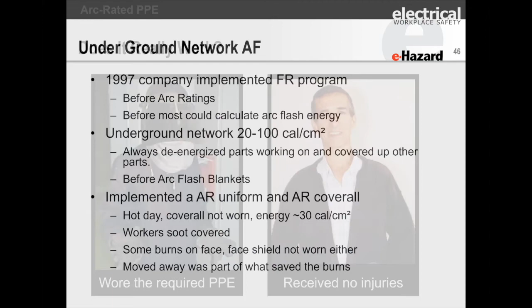Arc blast blankets are now becoming more used. They have failure points and details that can protect. In this case, we used this blanket, and after the test, the one on the right had no blanket intact, while the other one, the blanket was intact, and there was a big difference in body burn. If you can cover up the arc flash hazard of energized parts that can't be de-energized while working in a motor control center, in certain equipment, or in underground networks, you can get huge amounts of protection from these blankets.